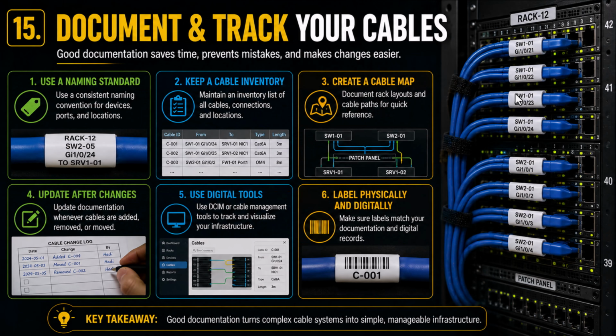Labeling and documentation should work together. The label tells you what you're looking at physically. The documentation tells you how that connection fits into the larger infrastructure. For example, if a switch interface goes down, good documentation can help you identify the cable, patch panel, or ODF position, remote device, and remote interface. This can save a huge amount of troubleshooting time, and whenever a connection changes, the documentation should be updated as well.